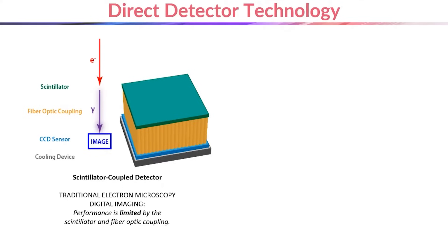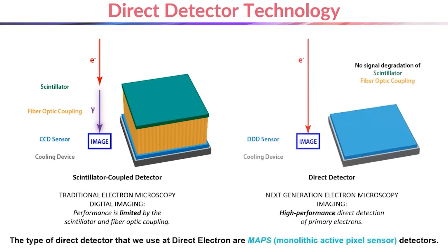Direct detectors with radiation hardened sensors that can be exposed directly to electrons to form an image were developed to overcome the limitations of scintillator cameras. The type of direct detector technology used at Direct Electron is called MAPS, which stands for monolithic active pixel sensor.